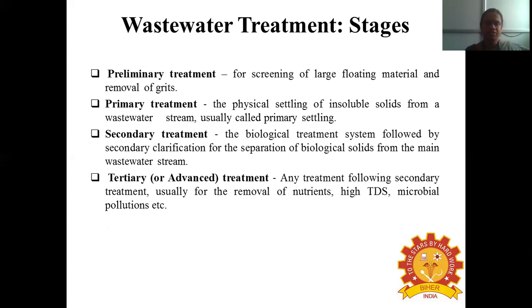Primary treatment is the physical settling of insoluble solids from a wastewater stream, usually called primary settling or primary sedimentation. Secondary treatment is the biological treatment system followed by secondary clarification for the separation of biological solids from the main wastewater stream. Tertiary treatment is the process which follows secondary treatment, usually for the removal of nutrients, high TDS, and microbial pollutants.